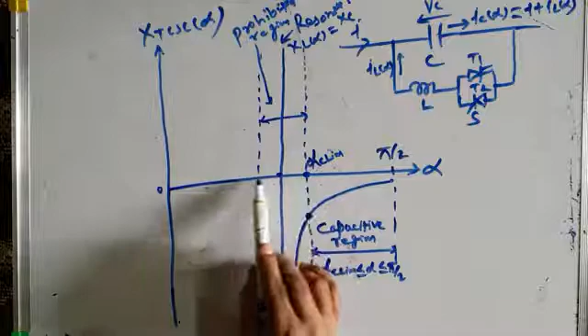If you operate your TCSC within this range, this is called the prohibited zone. This region is highly prohibited. Why is it a prohibited region? Because the range of alpha within this region makes the condition XL alpha equal to XC true, and resonance will occur. When resonance occurs, it becomes a parallel LC circuit and the reactance becomes infinite. So we should never operate our TCSC within this range of alpha.